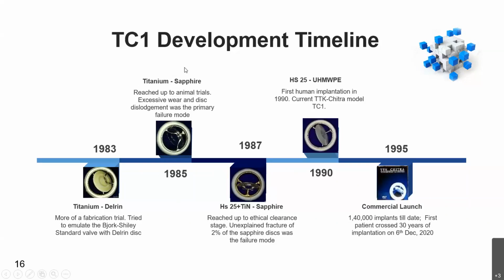So the first model came to the laboratory, and this particular model went through some of our studies and we found that this titanium is not up to the mark, in the sense that the wear rate of titanium is extremely high, and because of this the device will not last for the required service life. Incidentally, what we have to understand in this particular device is, even though it's a small device with very few components, this device has to work for 2000 million cycles. 2000 million cycles is 2 billion cycles. That is the number of times a human heart beats during a span of 50 years.